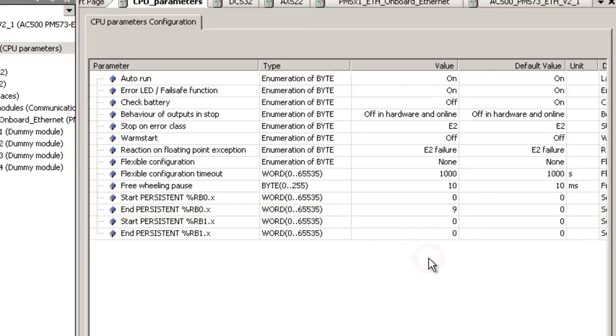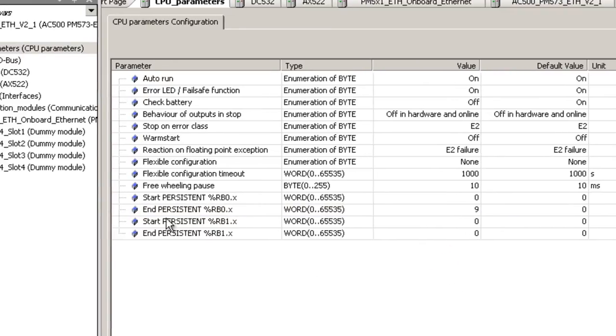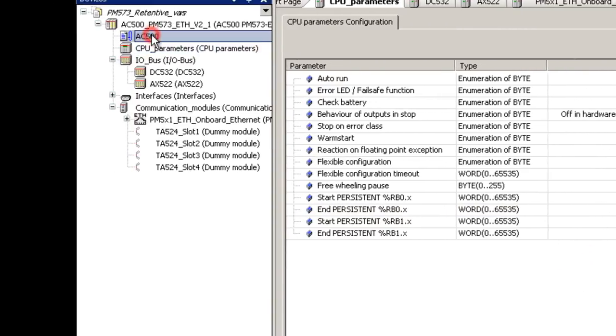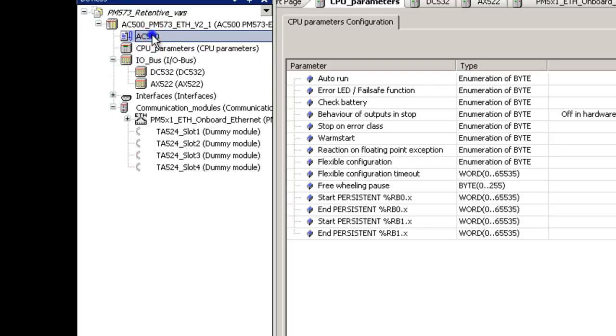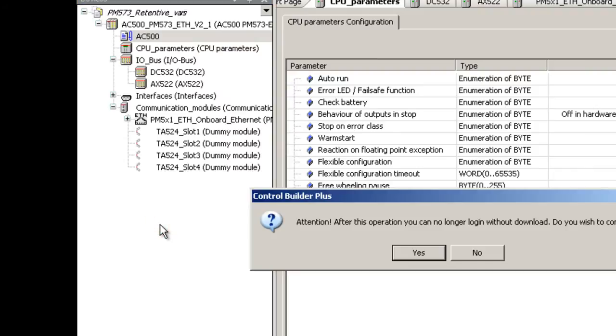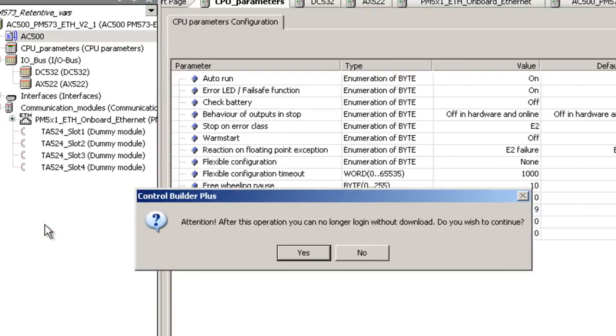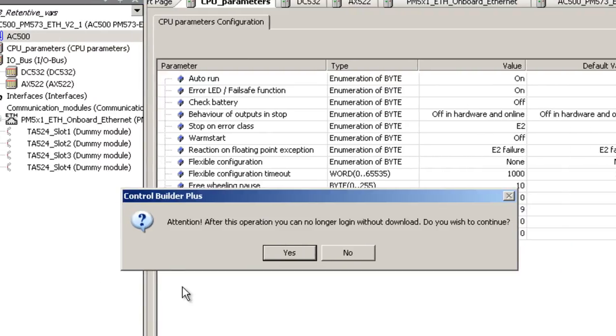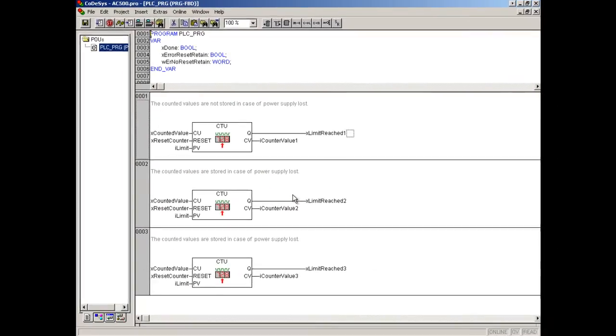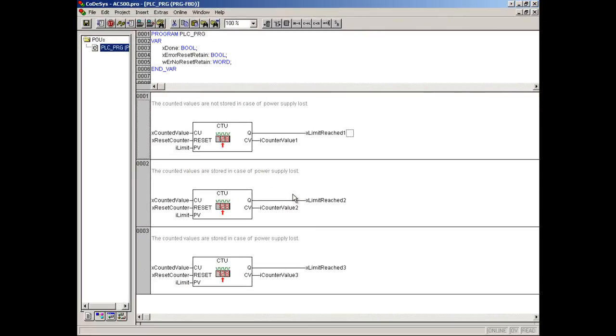We update the configuration file by right click on the branch AC500 and selecting the item, create configuration data. We acknowledge with OK the warning that by the next program transmission the CPU will be stopped. We needed this manual update because the project editor is already open. The editor will be automatically displayed.